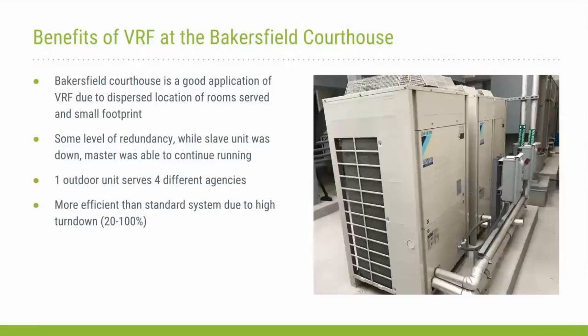Some level of redundancy. We experienced an outage of the slave unit, but due to the fact that these units are twinned together, the master was able to continue running, obviously at a reduced cooling capacity, but we were able to maintain continuous operations for our tenants. It's more efficient than a standard system due to the high turn-down capability of 20 to 100%.